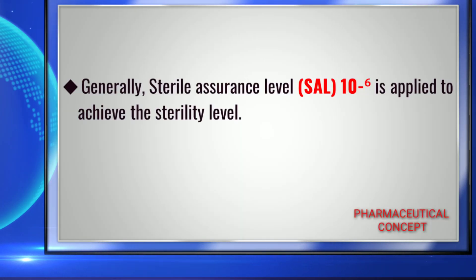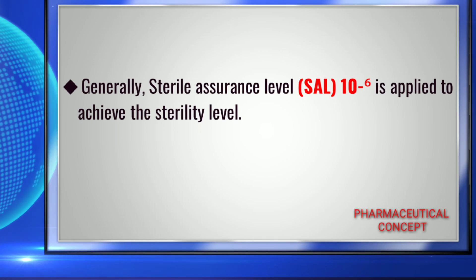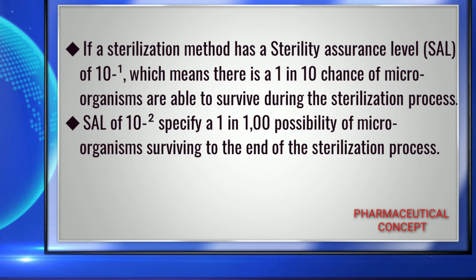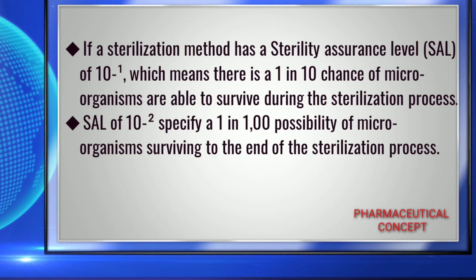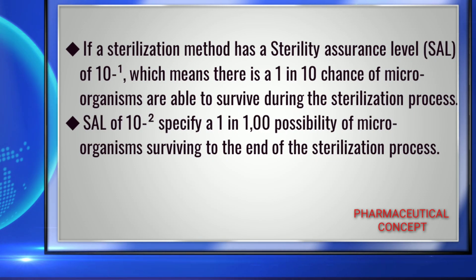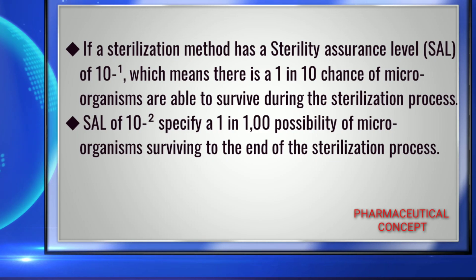Generally, a Sterility Assurance Level of 10 to the power of minus 6 is applied to achieve the required sterility level. If a sterilization method has an SAL of 10 to the power of minus 1, that means there is a 1 in 10 chance of microorganisms surviving the sterilization process. An SAL of 10 to the power of minus 2 specifies a 1 in 100 possibility of microorganisms surviving to the end of the sterilization process.